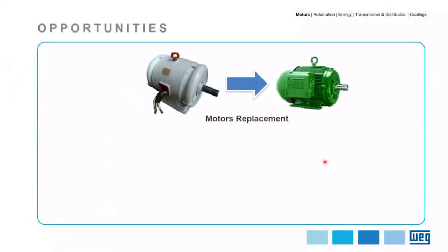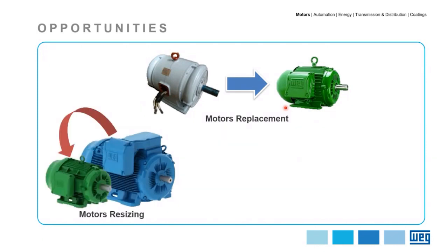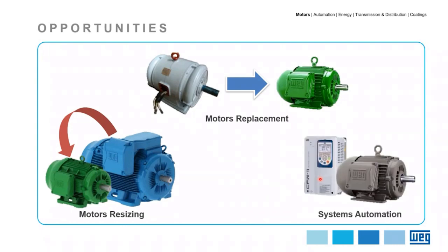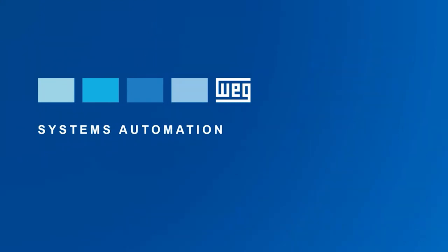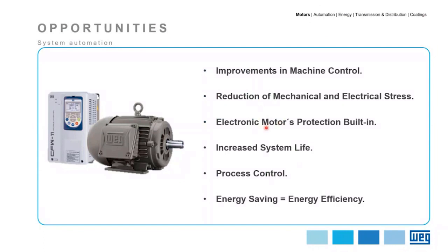If electricity is so important, how can we save it? First, we need to identify the opportunities. Some examples include replacing existing motors with new high-efficiency motors, motor resizing by applying motors as close as possible to the load demand — which will increase both efficiency and power factor — and applying a variable speed drive to the application, which is the main focus of this webinar. Beyond energy saving, other benefits of using a VFD include improvements in machine control, reduction of mechanical and electrical stresses, electronic motor protection built into the drive, and increased system life.